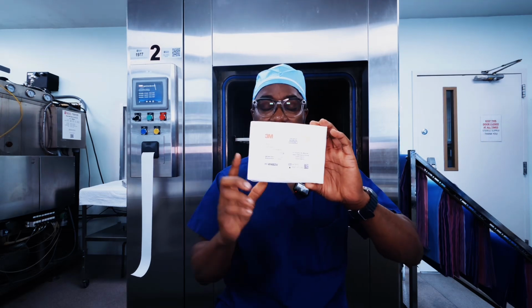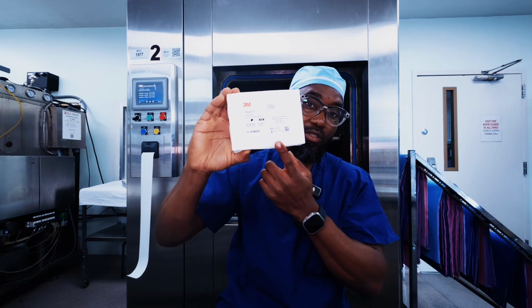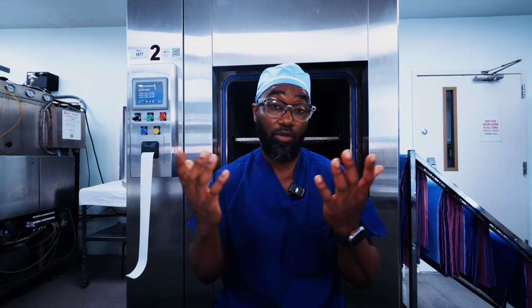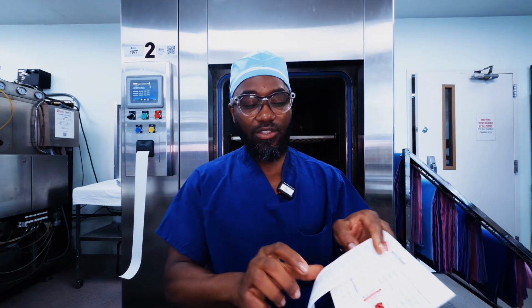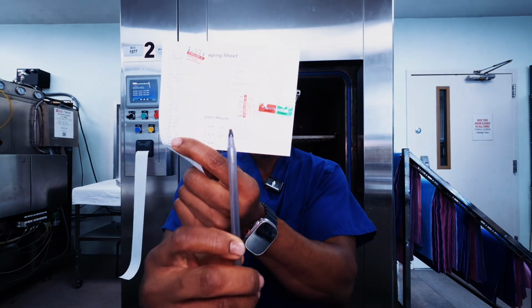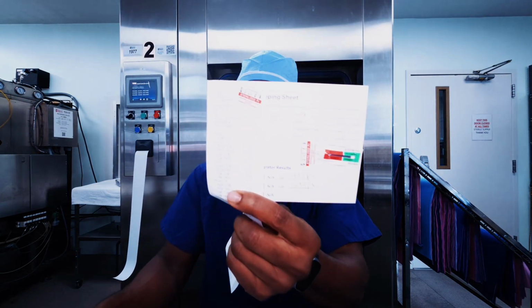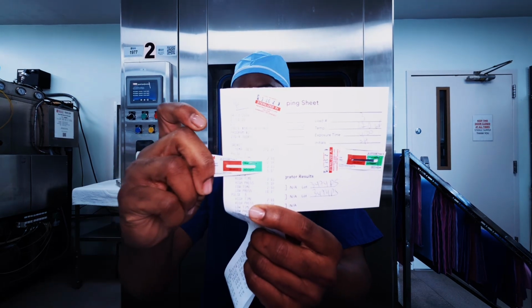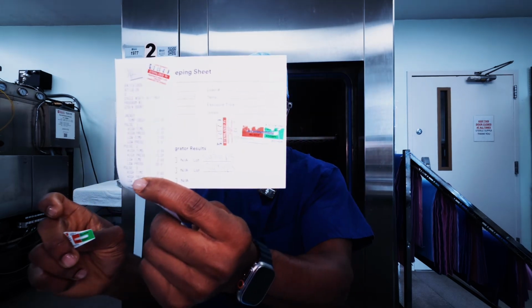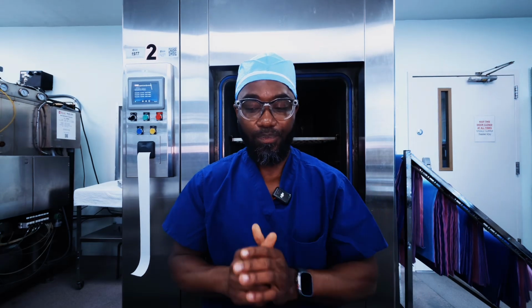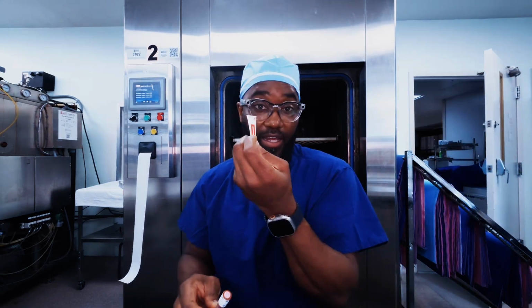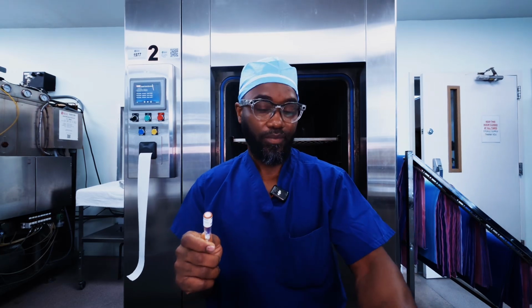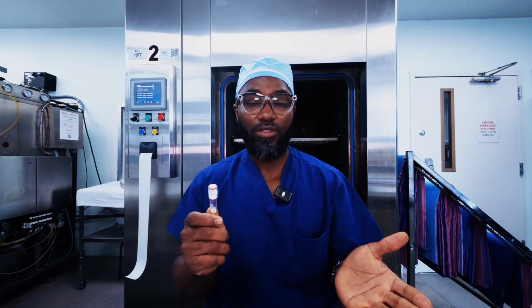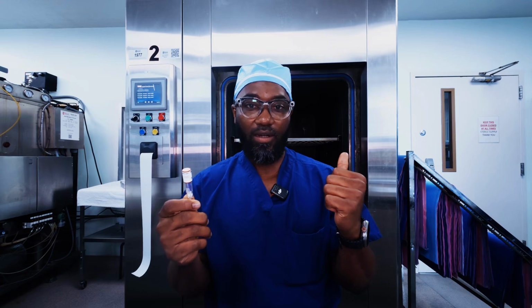After the sterilization process is done, we will incubate this biological spore, and once it's done, it should show that there is no life form or no growth within the ampoule of the biological test pack. This is what it looks like after the sterilization process. Your chemical integrated indicator changes color from white to black. If you notice the difference here, this is what it looks like before it goes into the autoclave, and this is what it looks like after it comes out. It has a change of color. These 2 items, your chemical indicator and your biological ampoule, will be read. Whether the result is favorable or unfavorable is how we determine whether the load within our autoclave has passed.